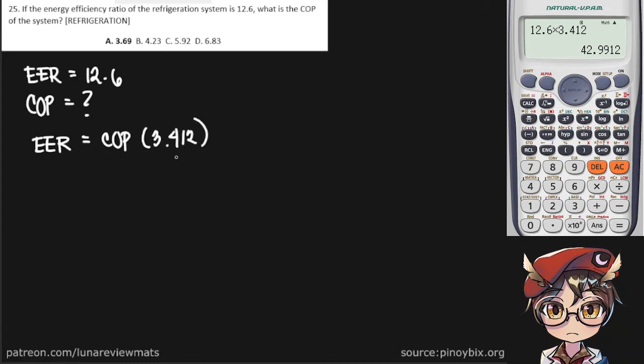Now, you might be asking why it is 3.412. Well, that's because COP is expressed in terms of kilowatts over kilowatts, while EER is expressed in terms of BTU per hour over watt. And this is simply the conversion factor.